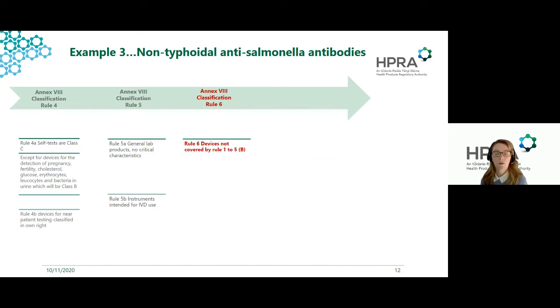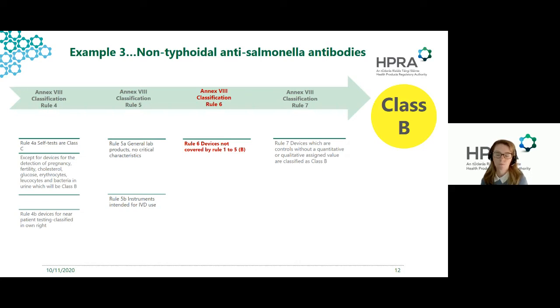So then finally, you come to rule 6, which we mentioned earlier. Rule 6 states that a device not covered by rules 1 to 5 will fall into class B. Have a look at rule 7 then - that's in relation to controls, if it's a control, so that would bring it into class B as well. But this is really based on rule 6, and this would end up being classified as a class B device.